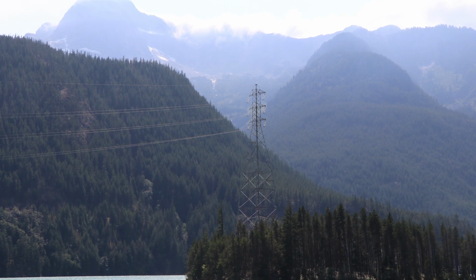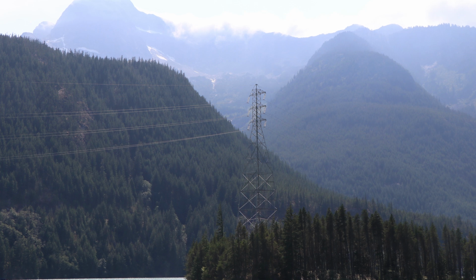And that's what allows us the ability to basically take them down to zero megawatts but keep them synced to the grid. When you're operating like that, how much water does it take, and how do you do the linkage? Say, for the next topic, a big grid disturbance happens, some load connects unexpectedly and you need more power, and your spinning reserves get called on. How do you get the water through? Because even if you're spinning at speed no load, once you need power from that unit, it does take water.